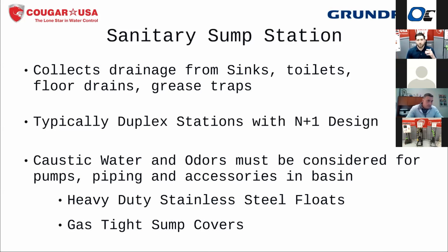So we would want to go with a 2 or a 3 float system here so that if our lag pump ran, we would immediately get an alarm so that we know that we have an issue. Last thing you'd want to do is get down to 1 pump on a sanitary station and not be getting that alarm and then have your second pump fail. And then you've got a really stinky situation on your hands there.